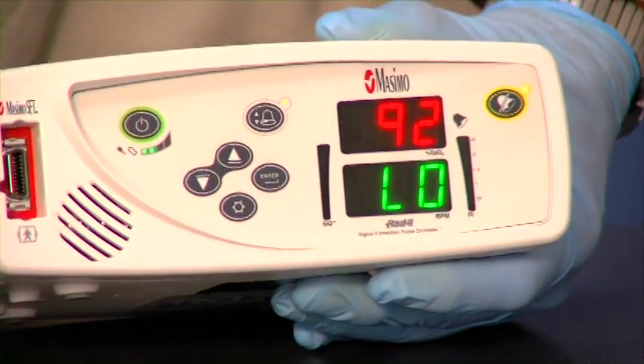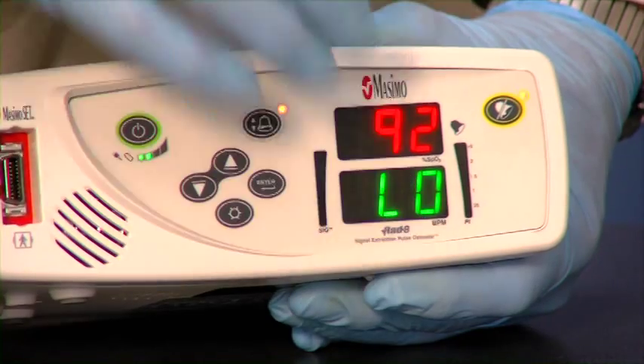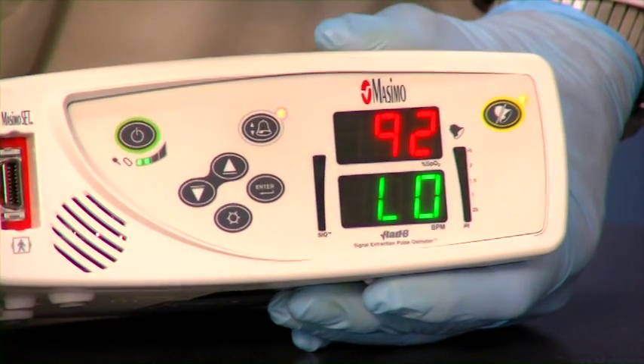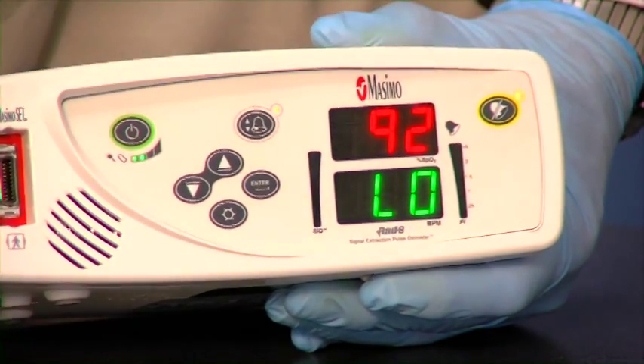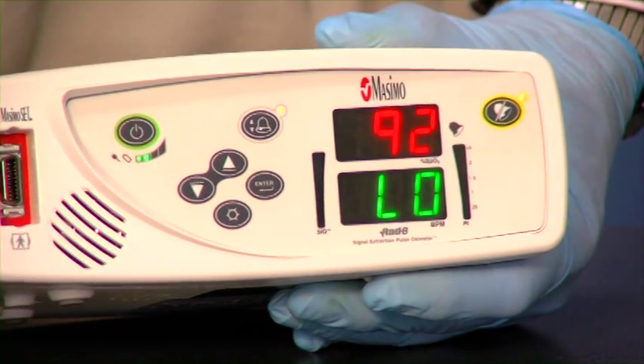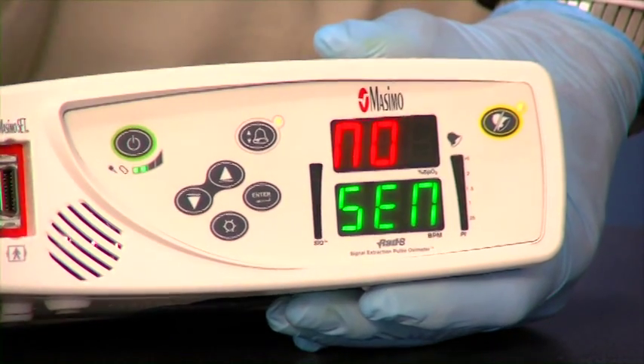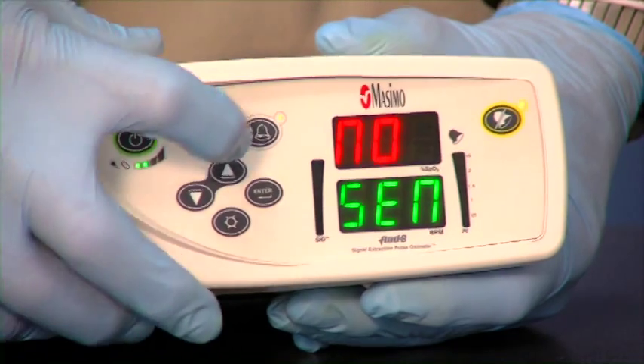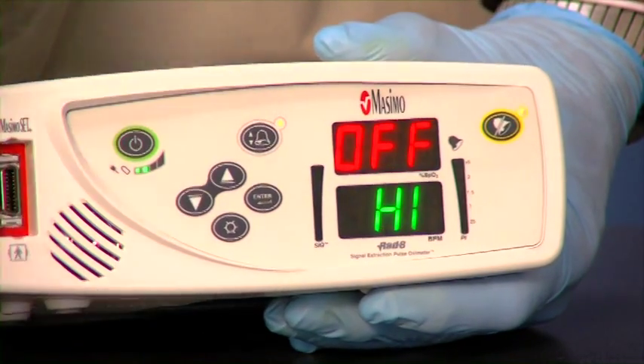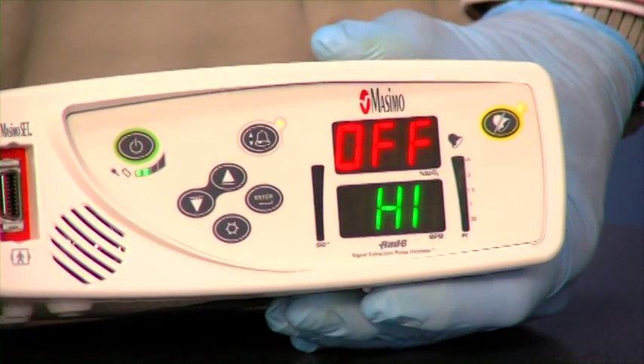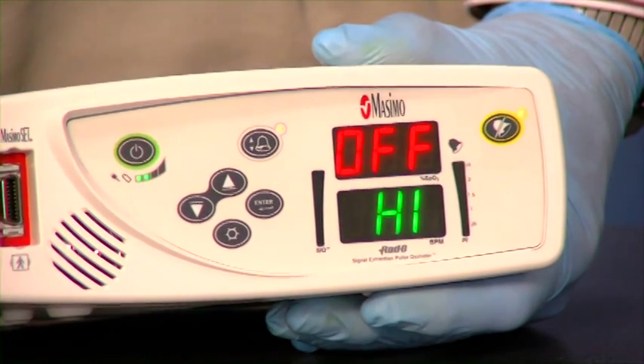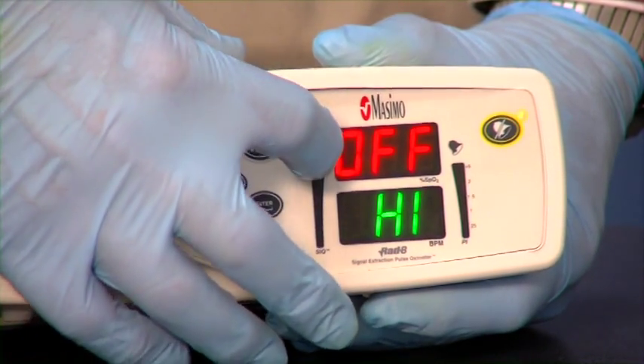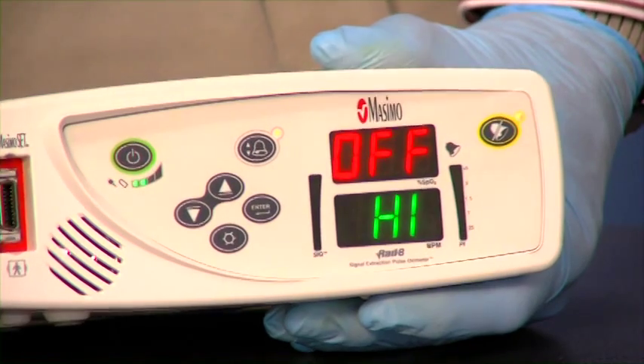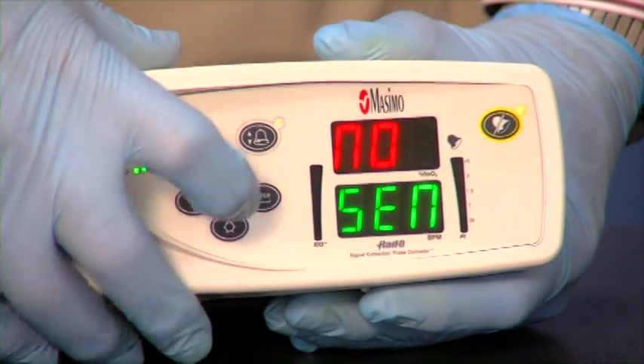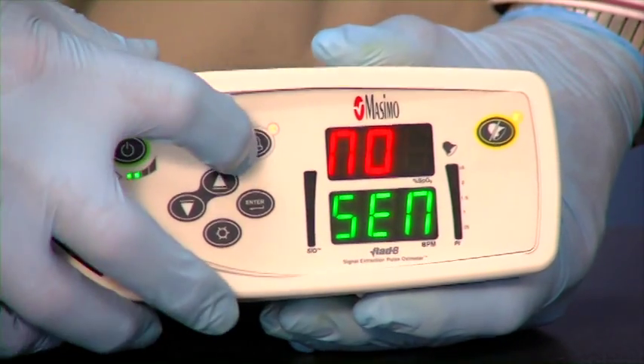So we press our selector button once, and it will show us what our low oxygen level is. Right now it's 92, which is our default setting, unless we receive instructions from the doctor to set it at something else. When we press that button twice, this takes us to our high oxygen level. So we leave this off, that would be the equivalent of 100%. So I don't think we're going to get it above 100%.